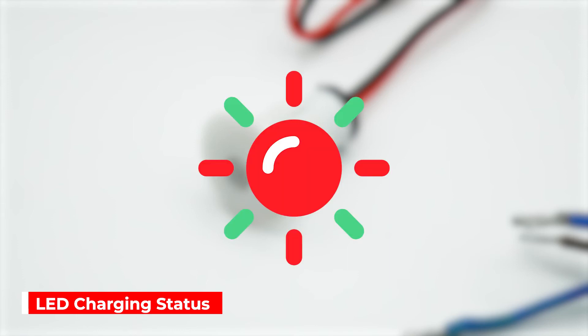A red and green fast flashing light indicates a battery failure. When slowly flashing, it indicates that there is a light source fault. A long bright flashing occurs when the battery is not charged following a self-test.